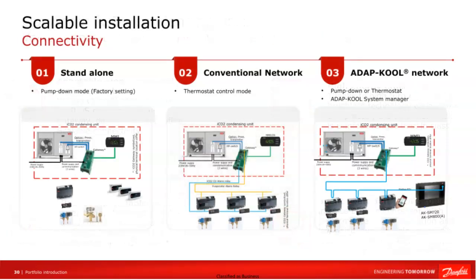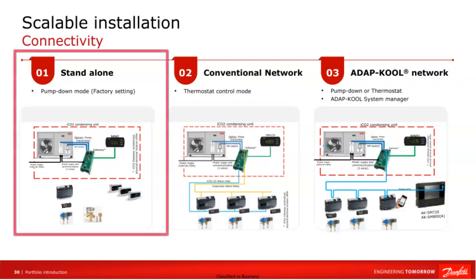On this slide, we present various possibilities of communication between the unit and the refrigeration system. Standalone operation of the unit without communication with the cooler. In this configuration, the unit operates independently. It controls operation based on internal parameters such as temperature and pressure. Features include pump down mode, internal controller, and local display.